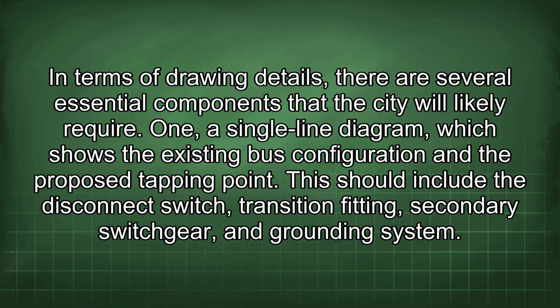In terms of drawing details, there are several essential components that the city will likely require. 1. A single-line diagram, which shows the existing bus configuration and the proposed tapping point. This should include the disconnect switch, transition fitting, secondary switchgear, and grounding system.